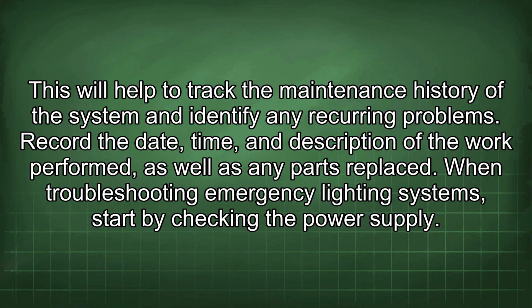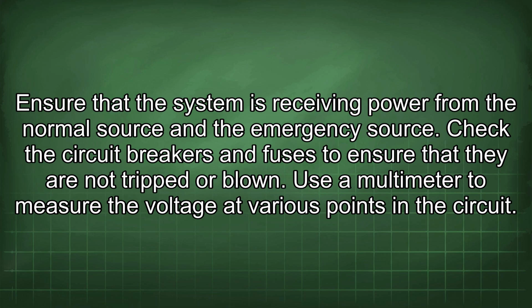When troubleshooting emergency lighting systems, start by checking the power supply. Ensure that the system is receiving power from the normal source and the emergency source. Check the circuit breakers and fuses to ensure that they are not tripped or blown. Use a multimeter to measure the voltage at various points in the circuit.